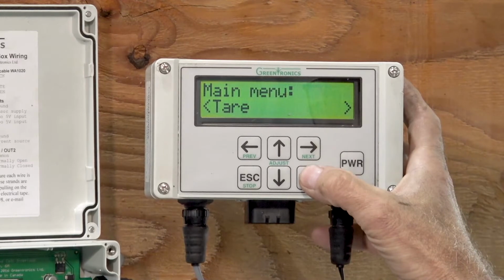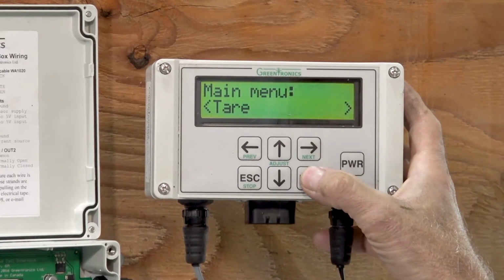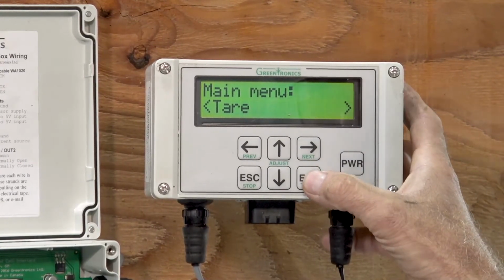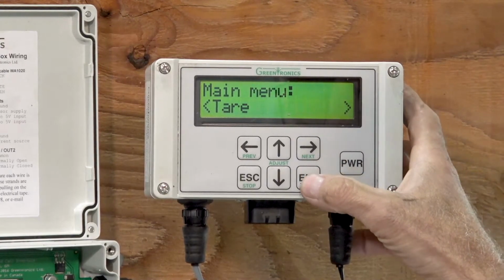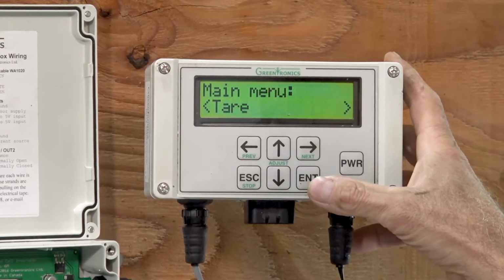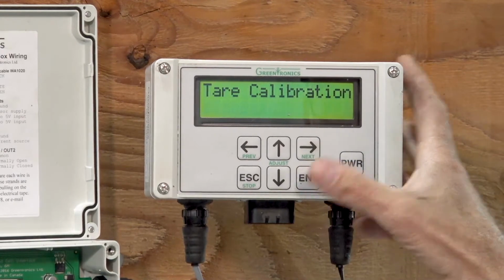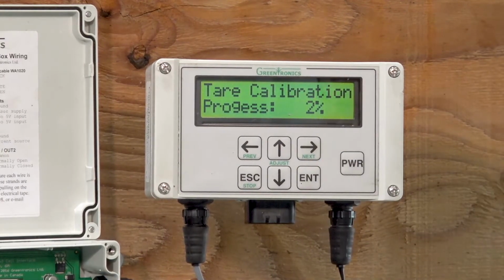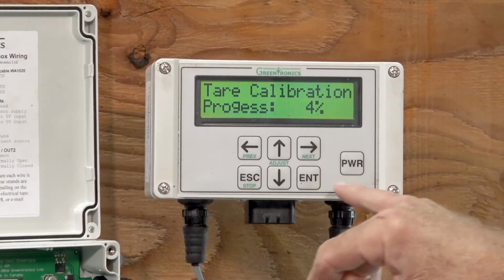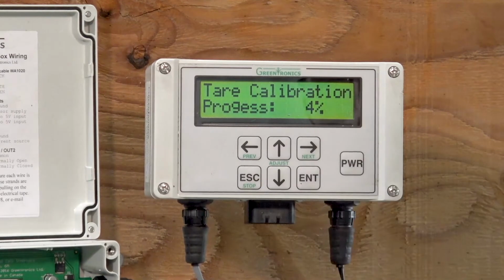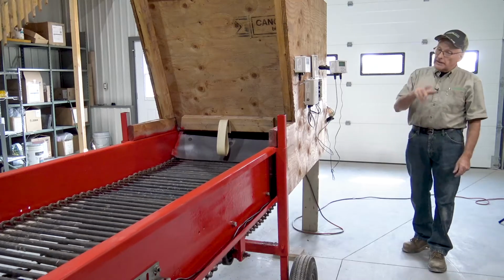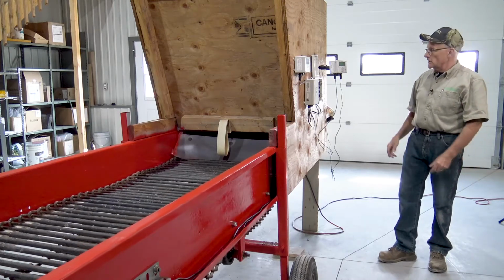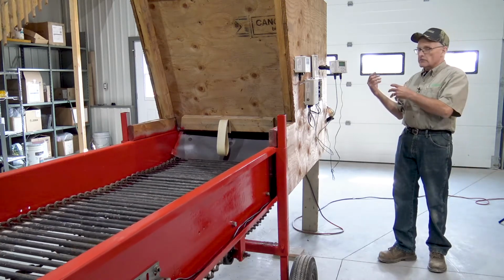Tare. And the conveyor is still running, so we can start that anytime. You don't have to be at a specific position to start a tare calibration. It's just that the conveyor needs to be running. And it will start, and the display will tell us how far along it is. So this will run to 100%, and then it will ask us whether we want to save the new value, and we click enter for yes. So now it's going to make another 3 full revolutions, and while it's doing that, it's storing the weight of the empty belt.